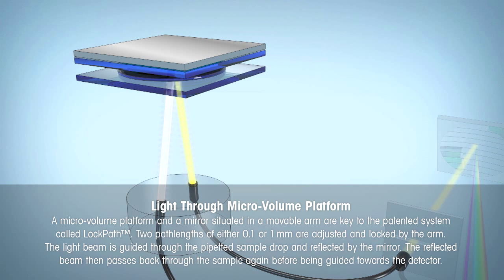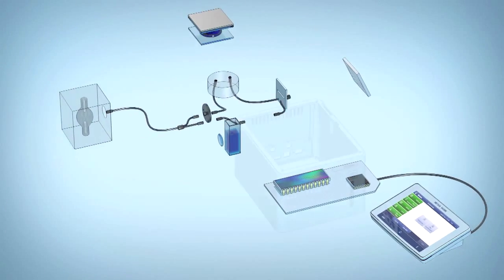Depending on the sample's characteristics, two pathlengths of either 0.1 or 1 millimeter can be adjusted and locked. The resulting pathlength is twice the physical distance between the surfaces of the optical cell and mirror. Because the beam is reflected and therefore passes through the sample solution twice, this principle reduces the amount of required sample.